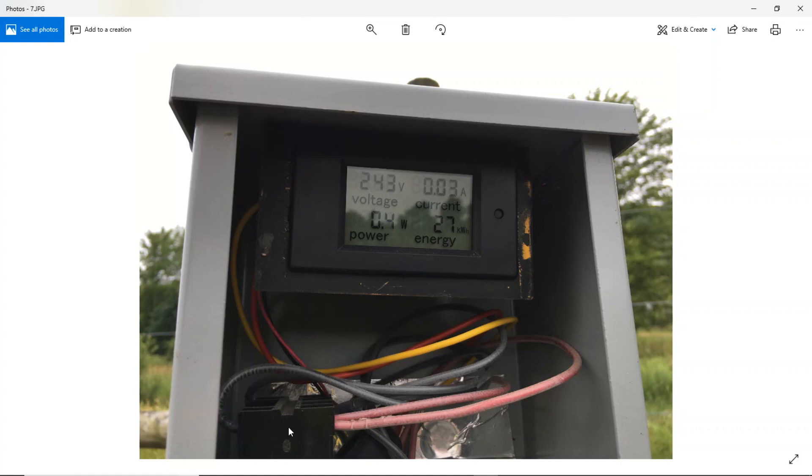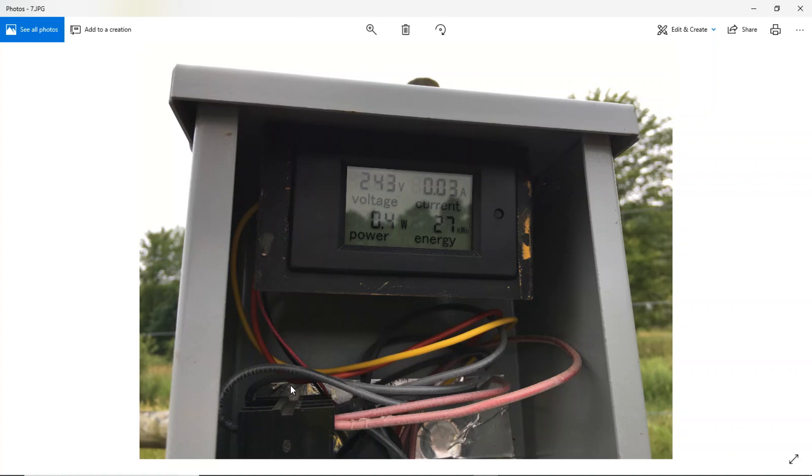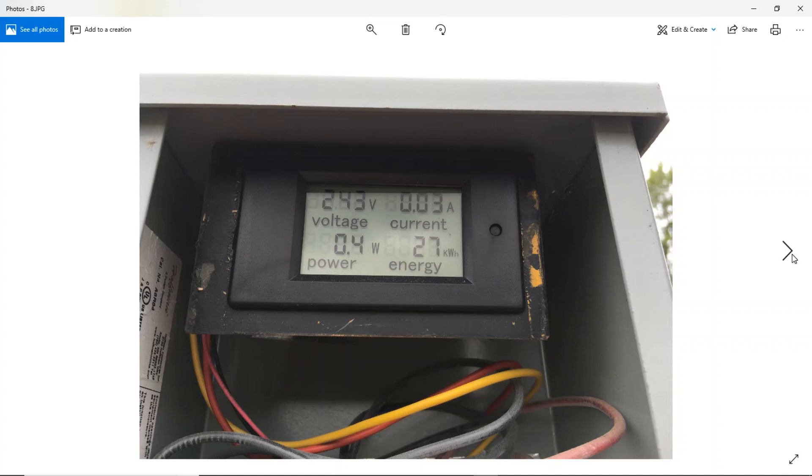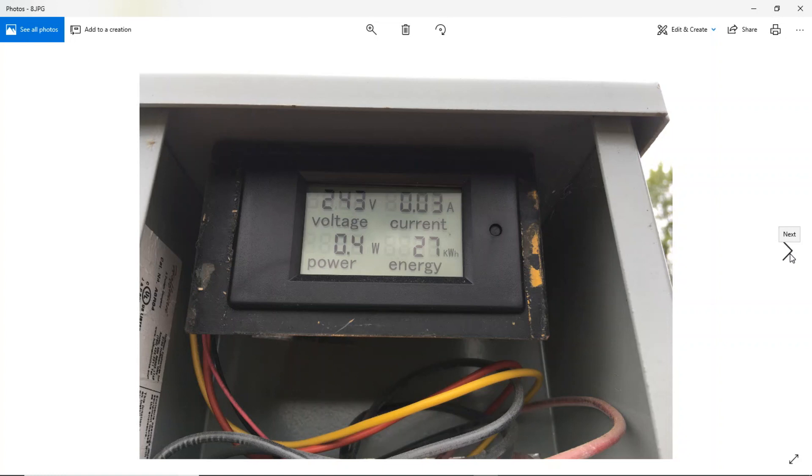What's really important here is this is connected to the pressure switch on the tank. When the pressure switch says it's low, it energizes this relay. This relay in turn passes that 240 volts on to the submersible well pump. This is what's doing the work, and it does it through the means to disconnect—the circuit breaker. Just a nice clear shot of that reading. It really comes in handy. When I had the other generator, I started having a problem. The numbers went crazy. It really helped me to troubleshoot the system without having to bring any test equipment with me. Just a screwdriver to take the cover off.